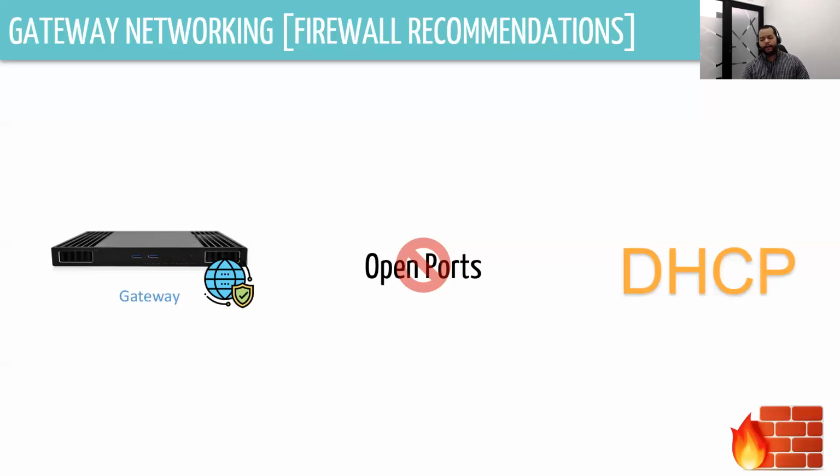And also, it is configured by default to have DHCP. That means that the gateway can get any dynamic address on itself when it goes to the site. It's important that if you're going to have a DHCP reservation, put that on the monitored devices, because if the monitored device's IP changes over time, then we lose track of it. It is important to have that on the firewall. If there is no DHCP available on the site, the IP needs to be communicated to Predictive before shipping the device, so we can install the static IP before it's going out.